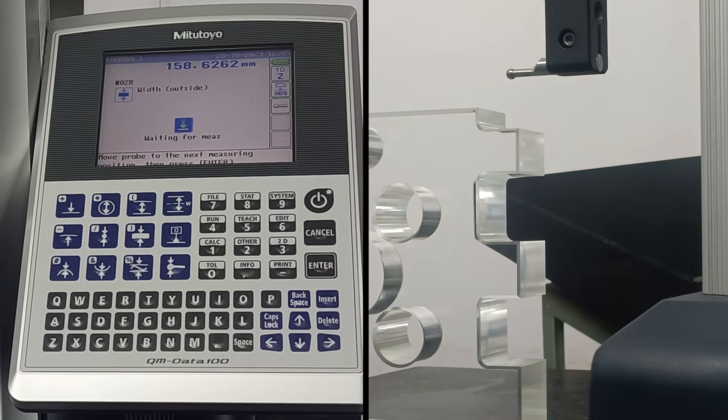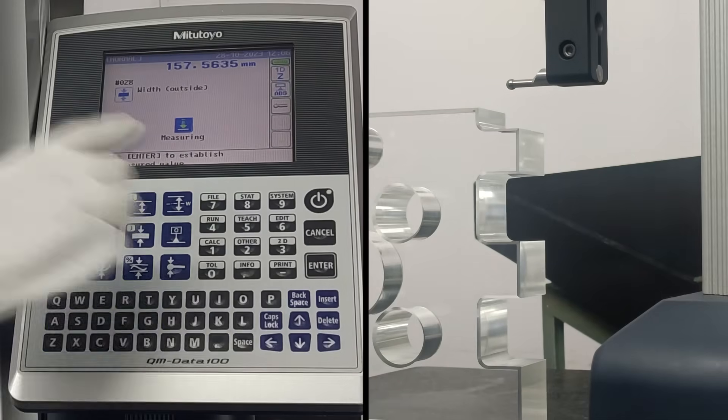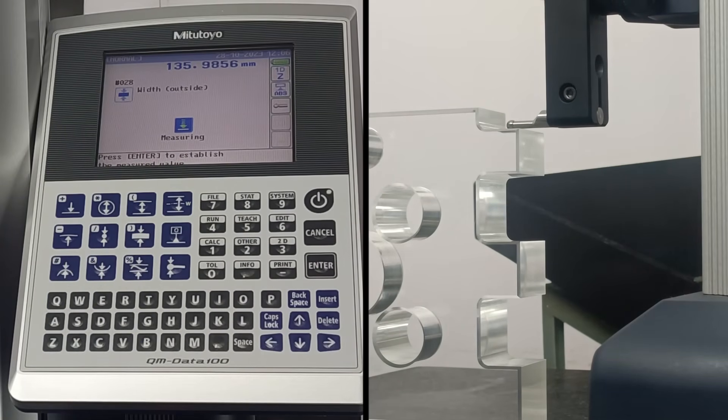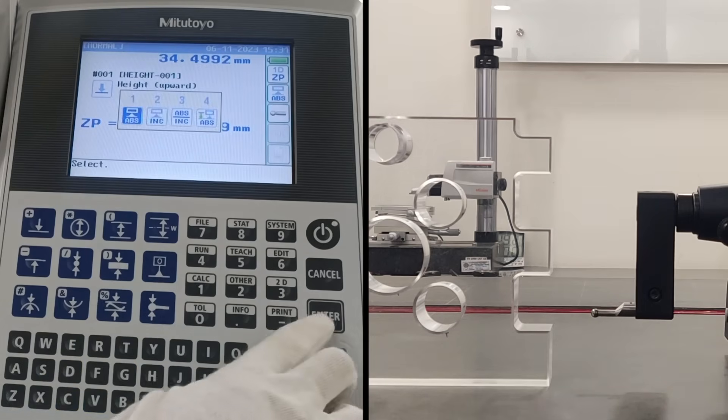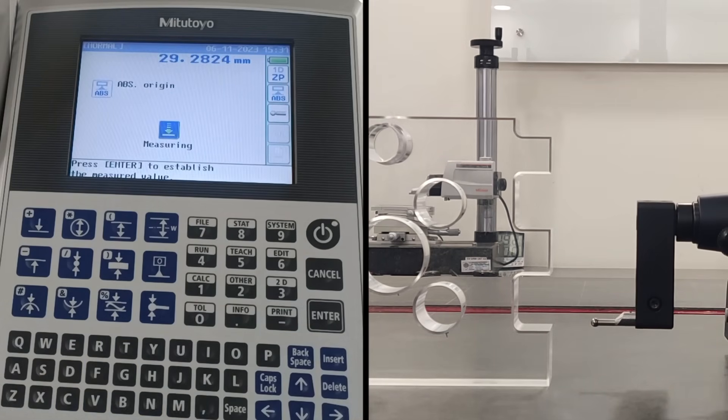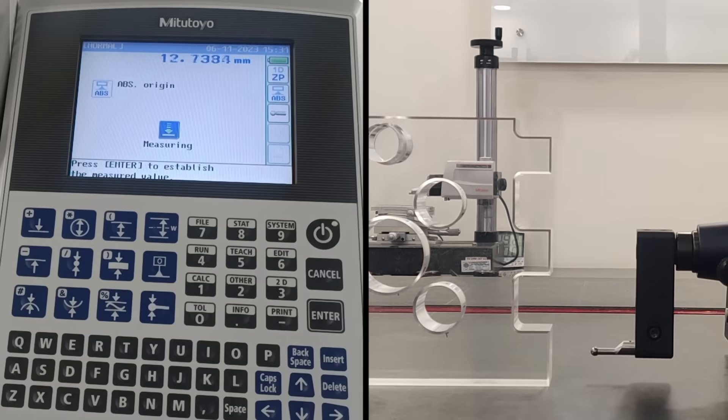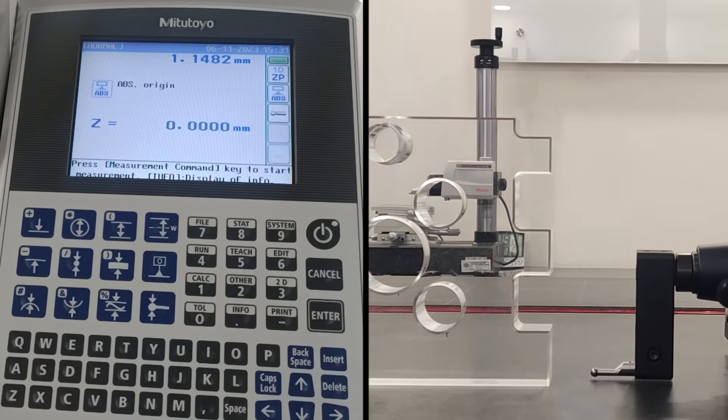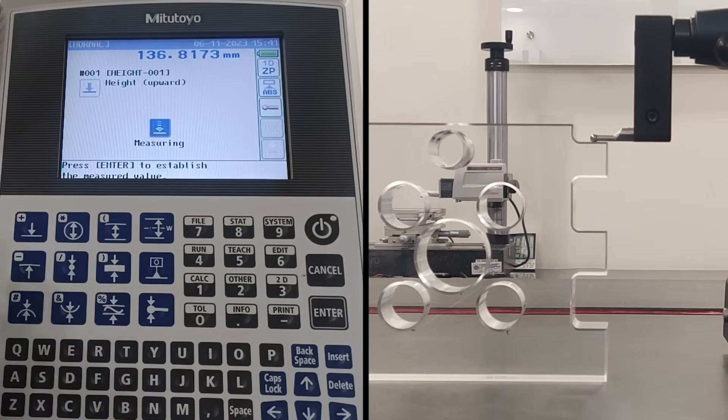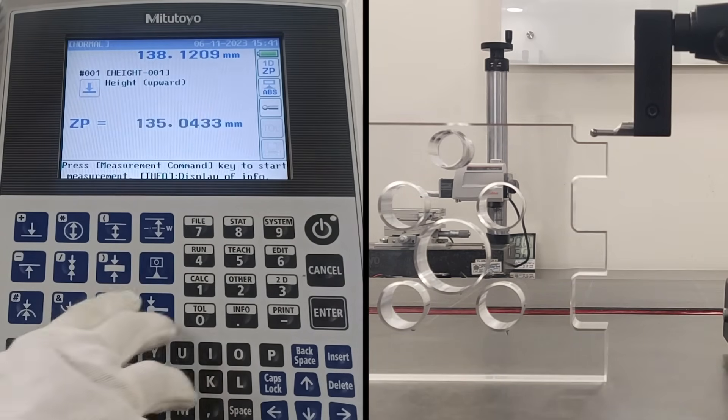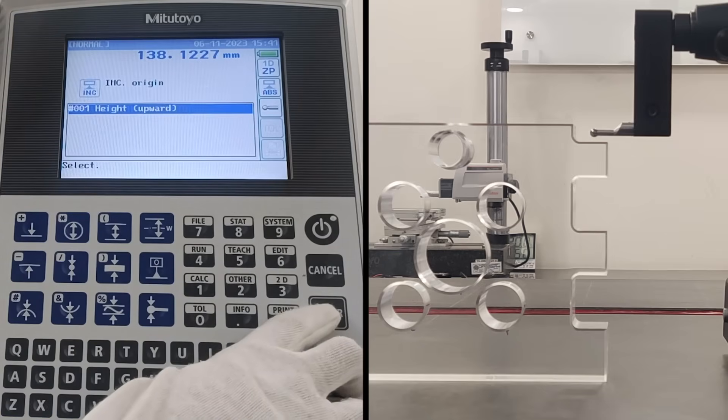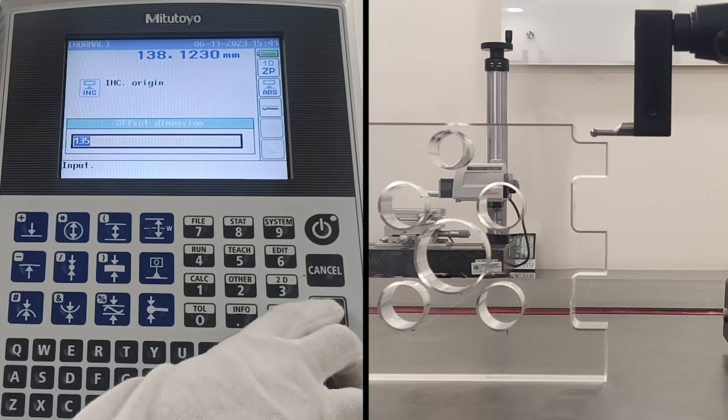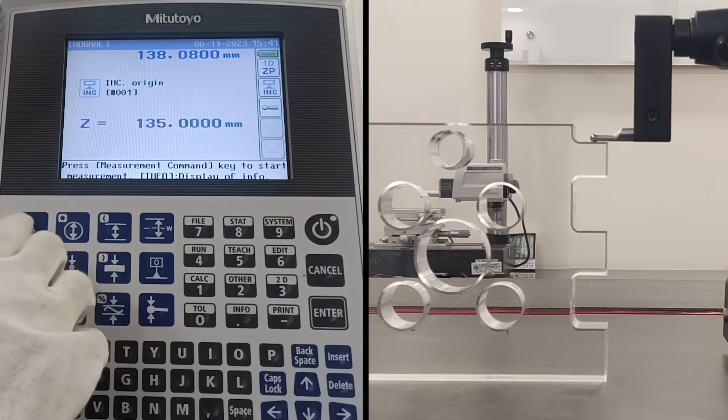The probe moves upward to measure the bottom surface and the probe moves downward to measure the upward surface. Absolute origin measures the upper surface of the surface plate on which the linear height is installed and sets the absolute origin. So, all measured distances will be calculated from this origin. To set incremental origin, it is necessary to first measure the position that is to serve as the reference point on the workpiece. Then offset dimension is entered, hence incremental origin is set.